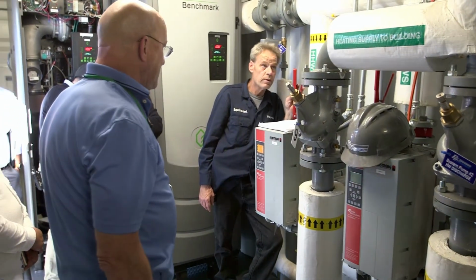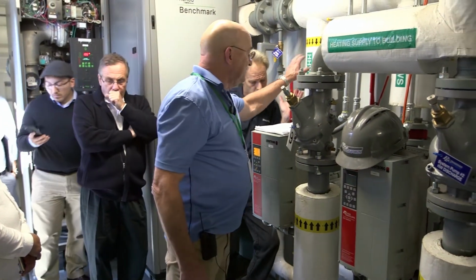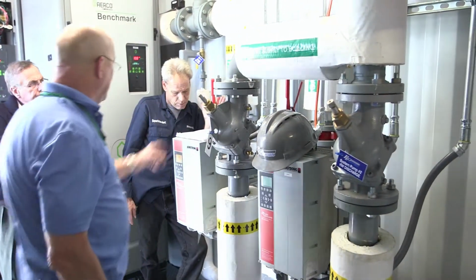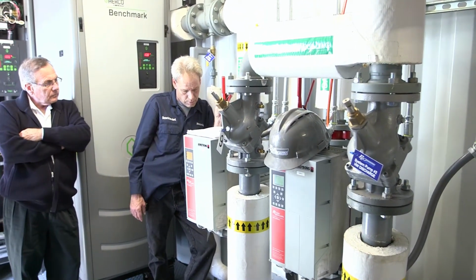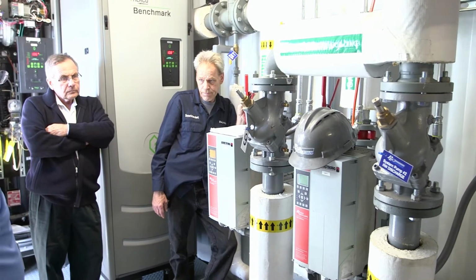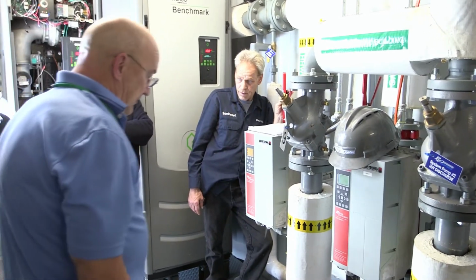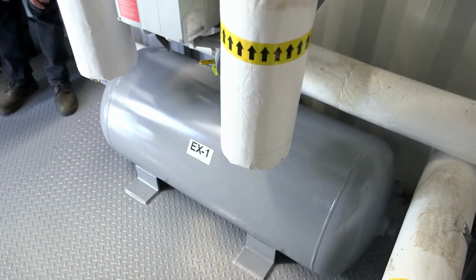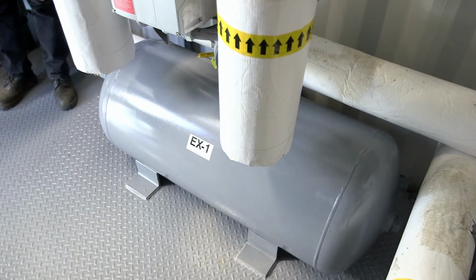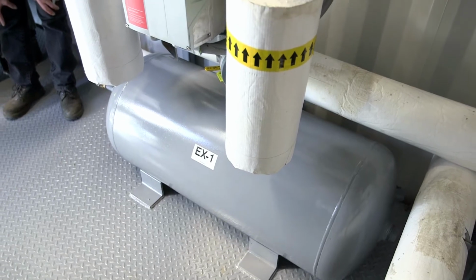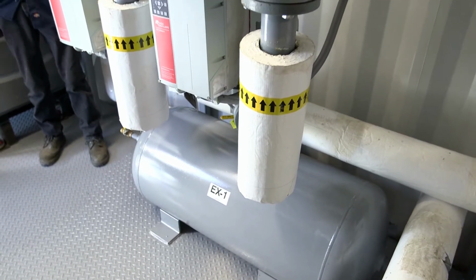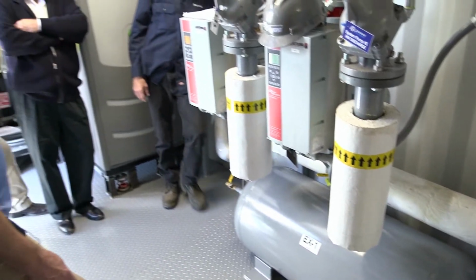Valves to shut off the supplies to the building are right here, these two red valves. That'll shut off any supply water going out to the building. Down here is your regular expansion tank for the boilers. Same thing as the tanks, as the boilers heat up and the system heats up, it's got to have somewhere to go. That's where it goes. And as it cools down, it goes back to the tank.